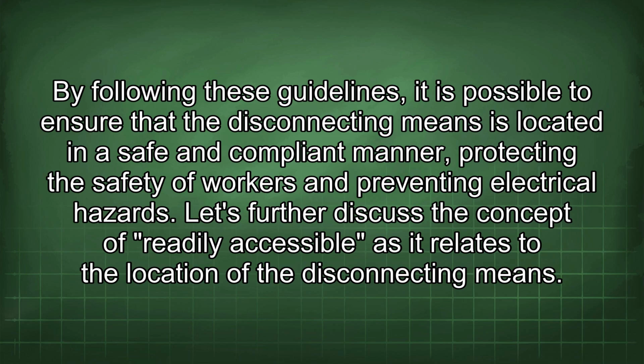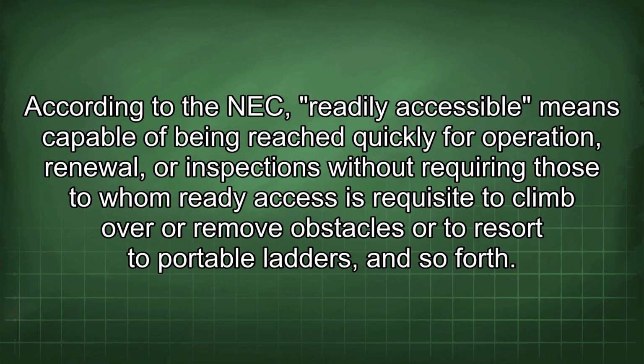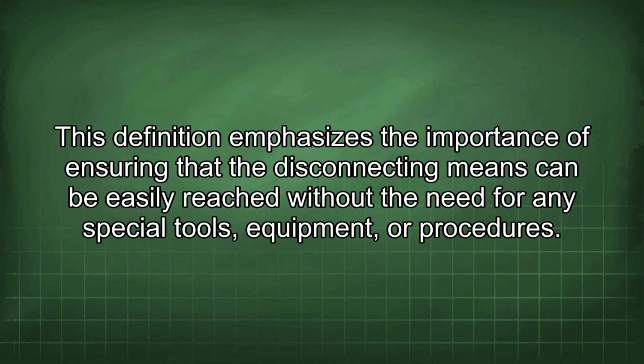Let's further discuss the concept of readily accessible as it relates to the location of the disconnecting means. According to the NEC, readily accessible means capable of being reached quickly for operation, renewal, or inspections without requiring those to whom ready access is requisite to climb over or remove obstacles or to resort to portable ladders, and so forth. This definition emphasizes the importance of ensuring that the disconnecting means can be easily reached without the need for any special tools, equipment, or procedures.